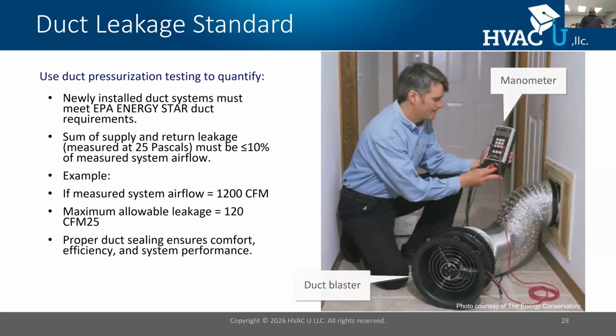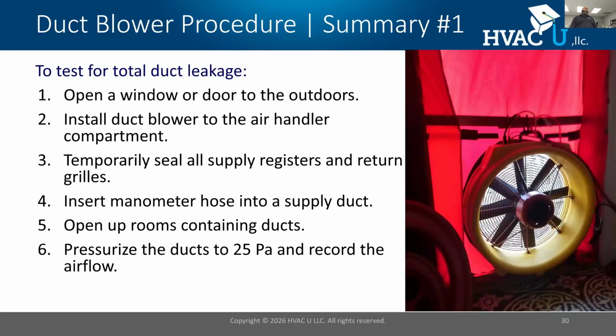So, for example, if you measure 1200 CFM for airflow, and this will be derived from the data plate on your system. If I have a 3-ton system and it's 400 CFM per ton, that's roughly 1200 CFM. If I pressurize a duct to 25, I will be looking for a leakage rate less than 10%. And this will let me know that the ducts are indeed above whatever standard you're trying to measure, right? And if you don't have the number below 10%, then you need to seal the ducts and then reperform the test, right?